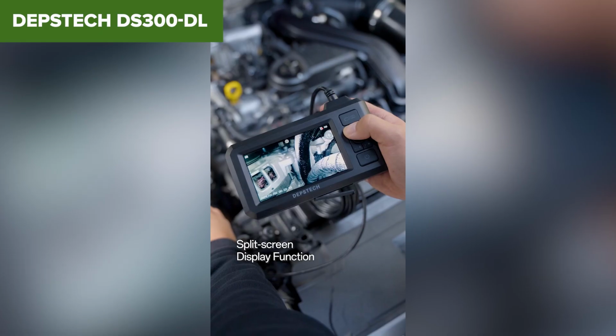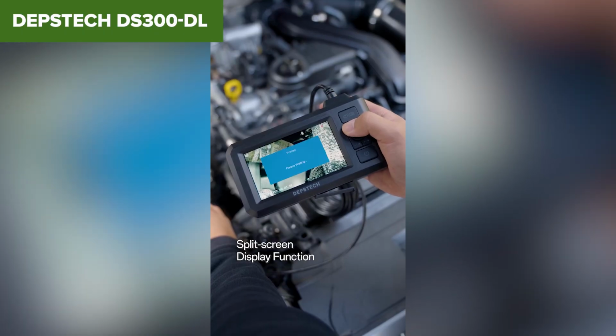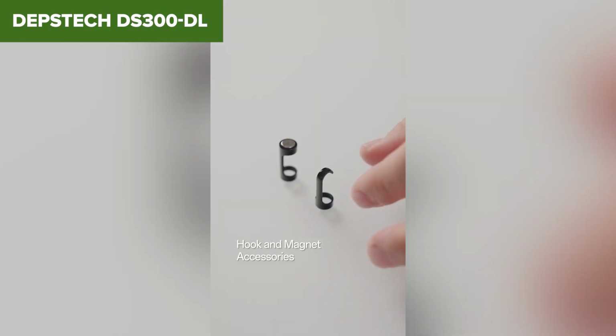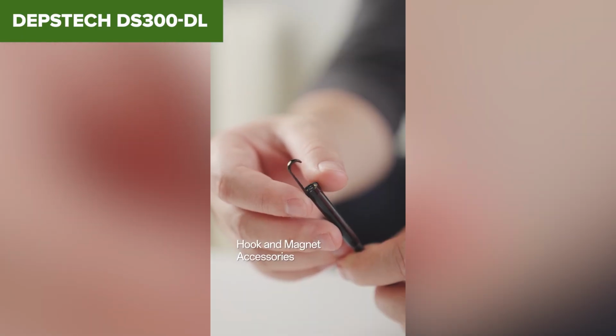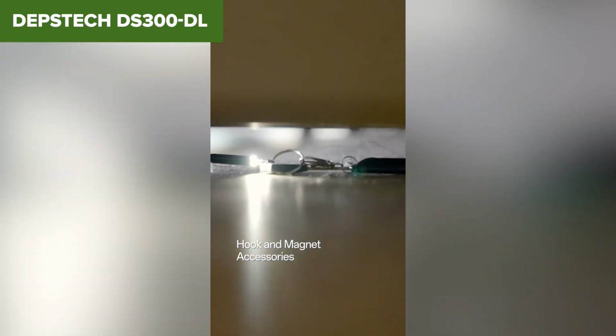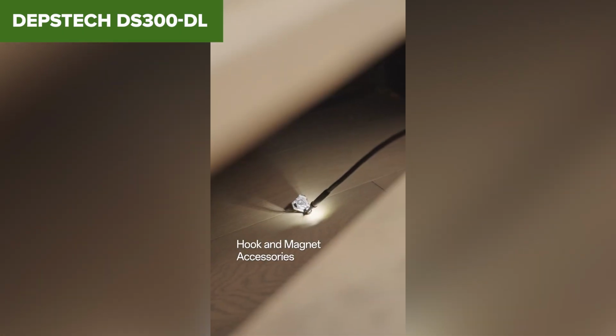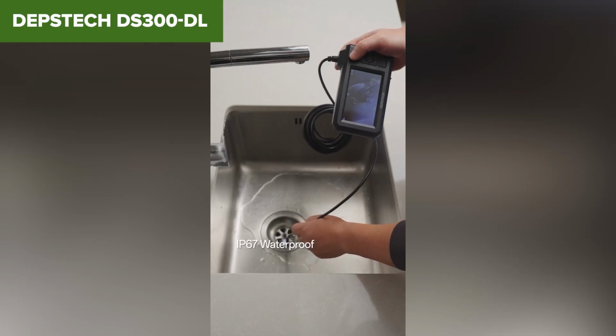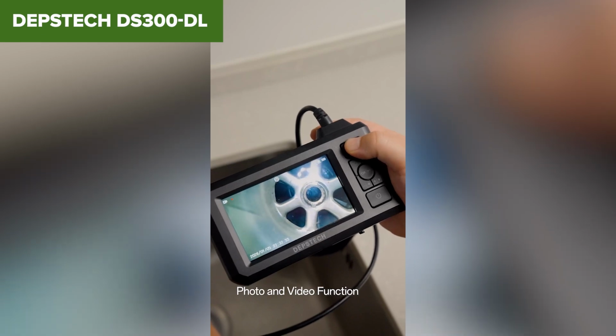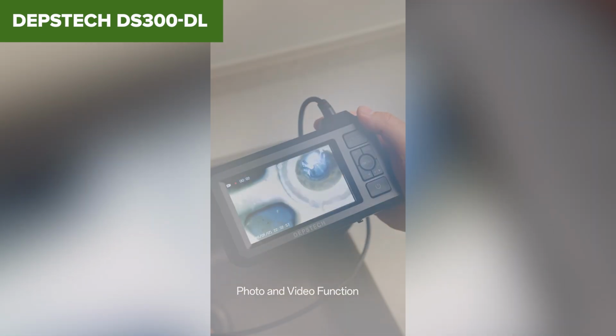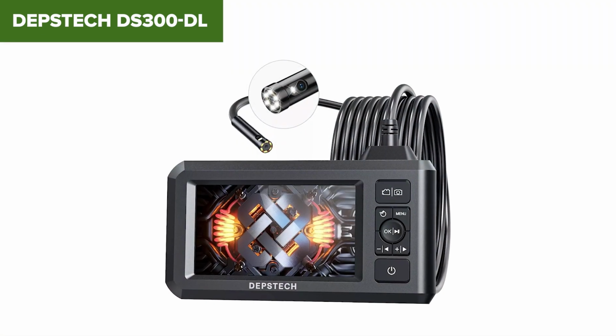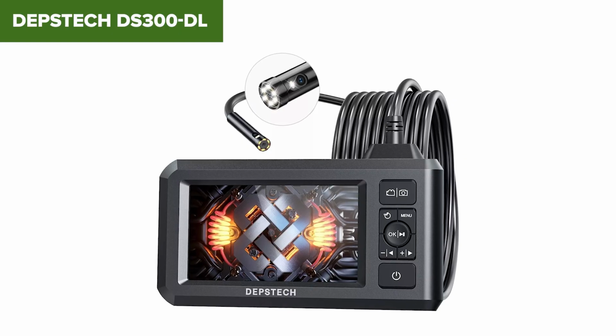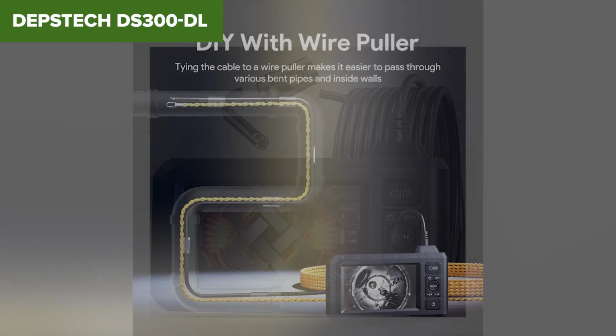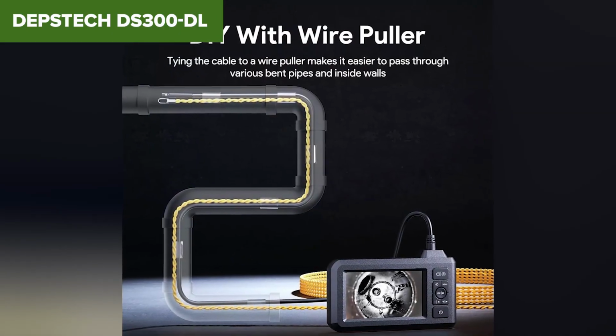So why is it not number one? Because it still lacks articulation. The dual lens design helps a lot, but it is not the same as physically steering the tip where you need it. If you have to inspect around a bend or get a better line of sight in a cramped area, the top-ranked product has a real advantage. This one is also still built around fixed focus ranges, so it works best within those close inspection distances.